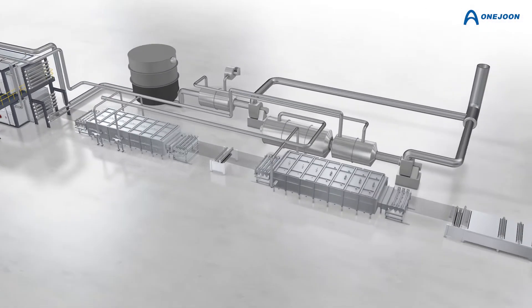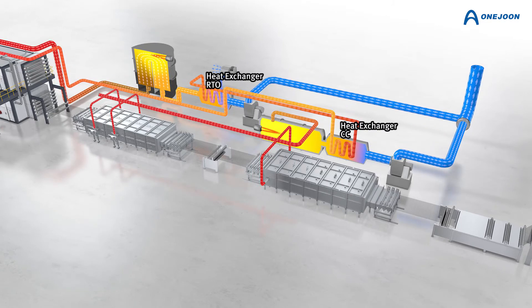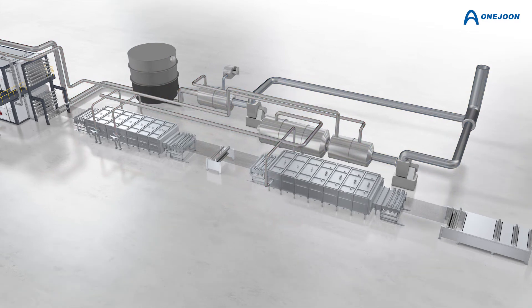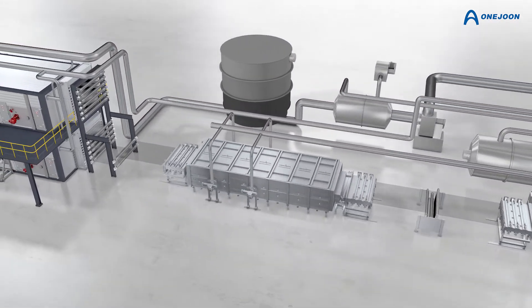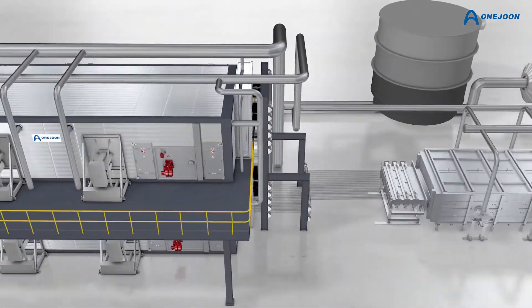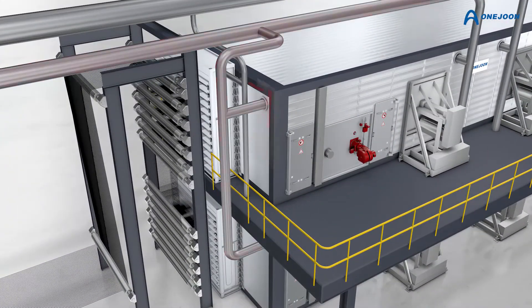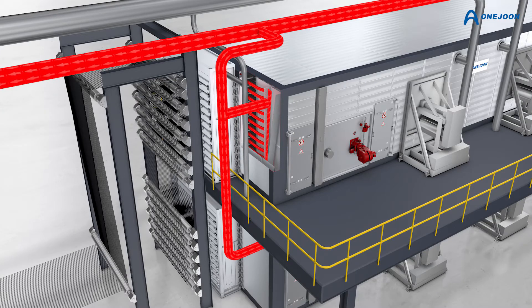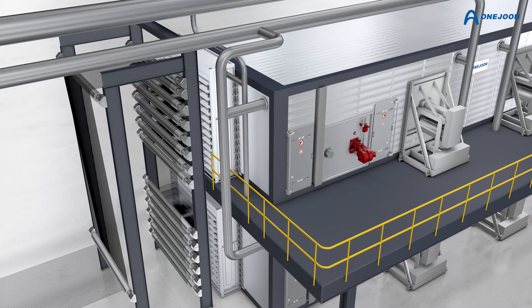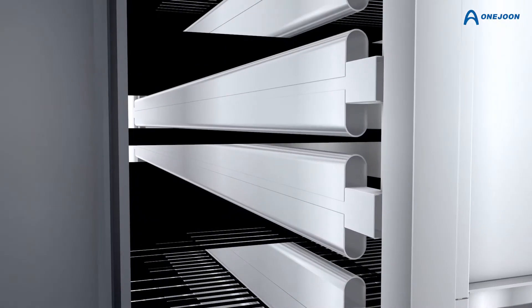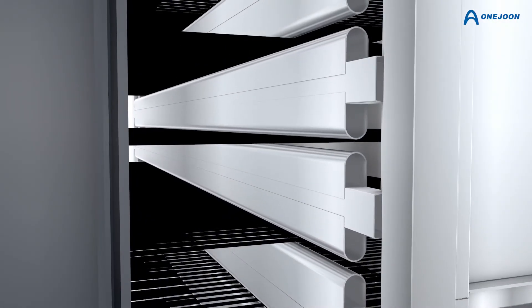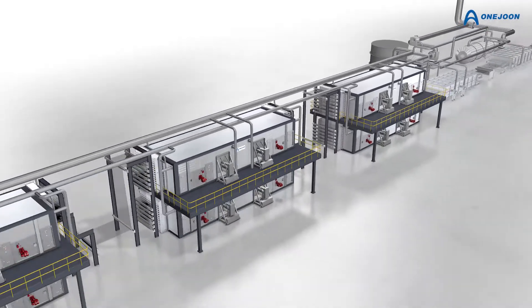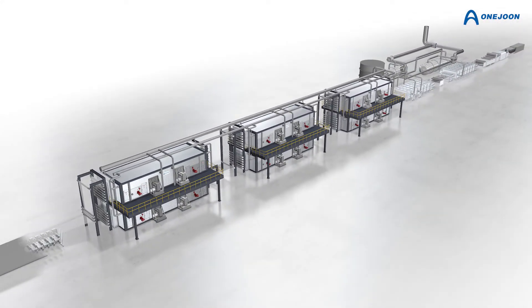The process requires a continuous fresh air supply. Using an air-to-air heat exchanger after the abatement system, the fresh air is preheated and delivered to the front of the end seals. This energy is utilized to significantly reduce the overall energy consumption to heat the ovens by up to 50% during operation. Vestibules are provided on each end of the oven to capture any fugitive emissions from the fiber prior to exiting the oven. A fully automated louver system provides the best access for fiber handling and helps reduce the overall energy consumption.